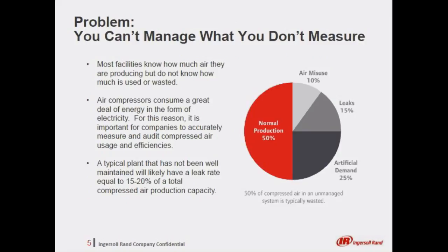Many facilities have at least a general understanding of how much air they're producing, but many haven't explored how much is actually used or wasted. Air compressors consume a great deal of energy in the form of electricity, and for this reason it's important for companies to accurately measure and audit compressed air usage and efficiencies. A typical plant that hasn't been well maintained will likely have a leak rate of about 15 to 20% of total compressed air production capacity, and this combined with the misuse and artificial demand results in only about 50% of air being used for normal production.